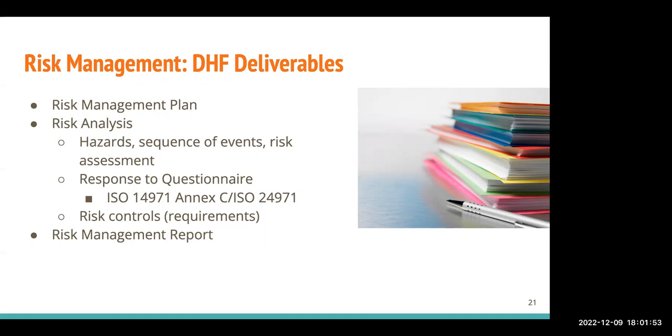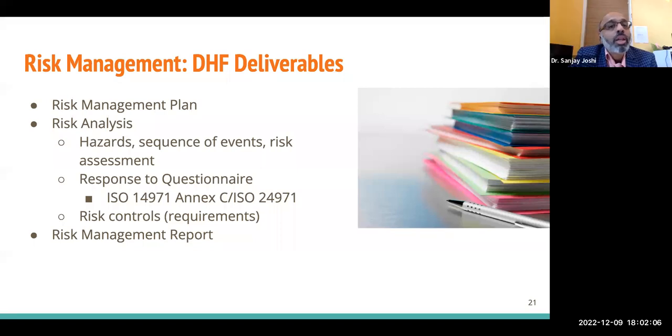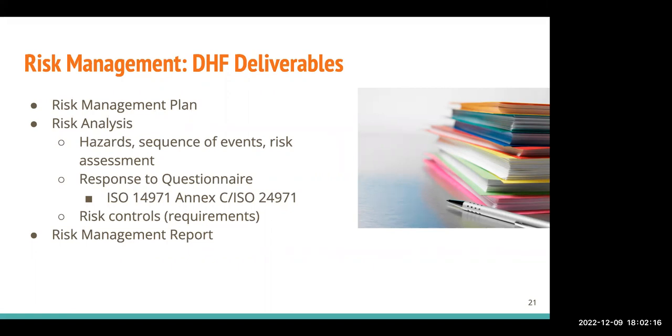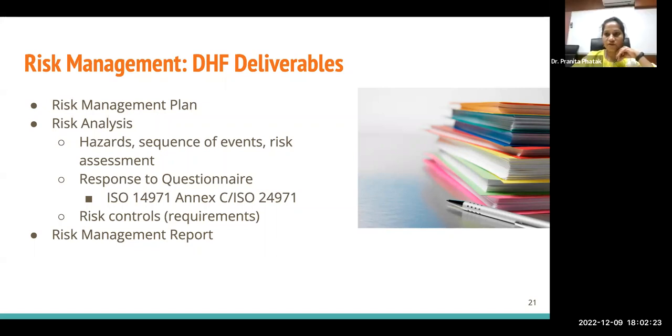But for that non-acceptable risk, do I have to mention whether, after redesigning the product, we are able to work on this risk, or it is not necessary? So the risk that you talk about, Manjari, in the risk management report is always after the mitigation, after you have done all the design changes to address the risk. It's not before. Okay. Yes. Thank you. Yeah, thanks, Manjari.